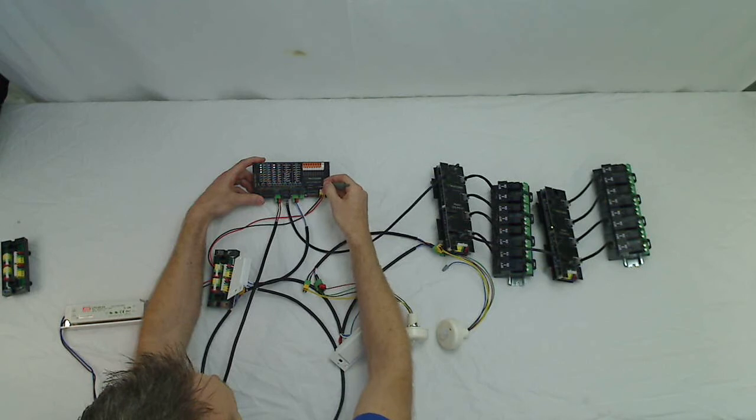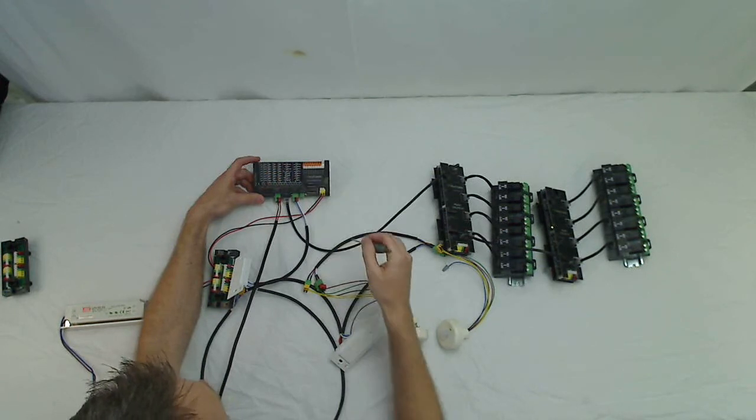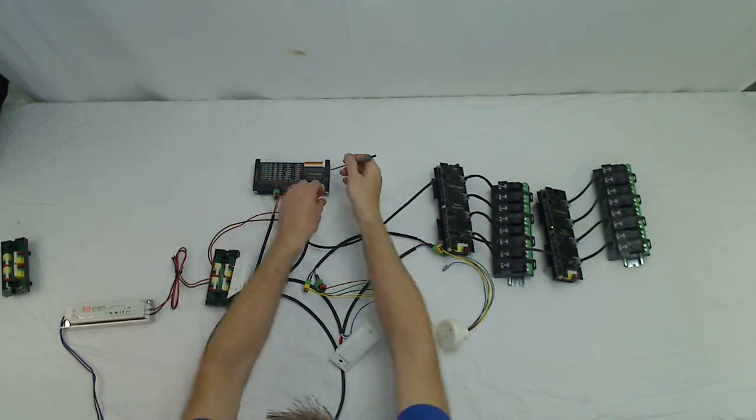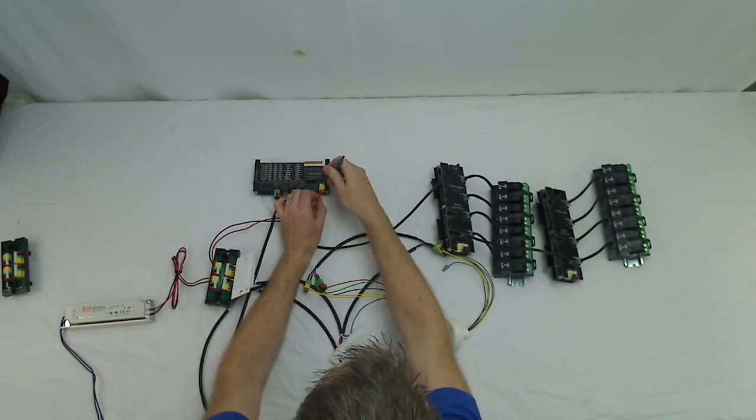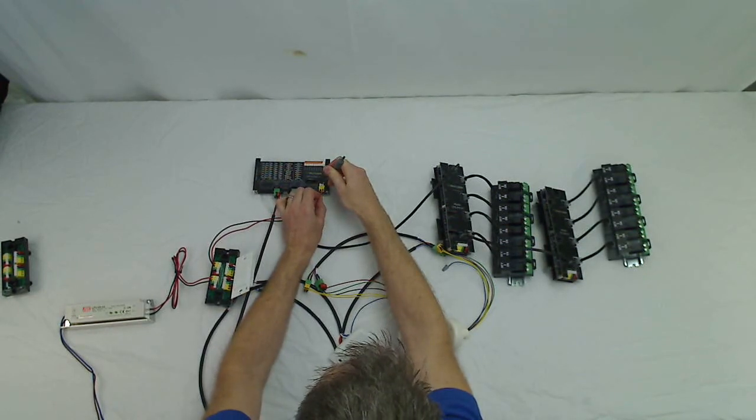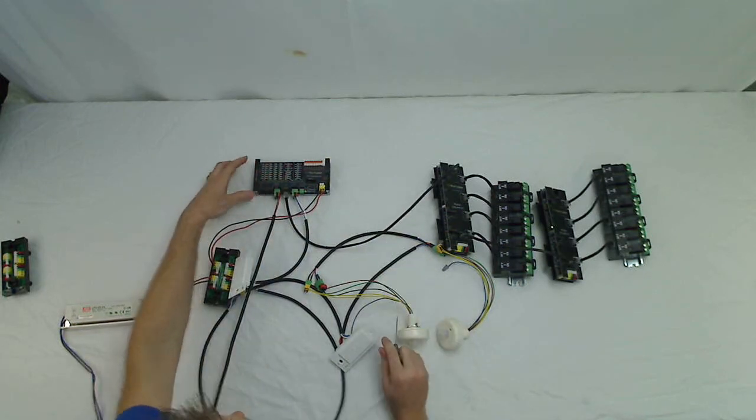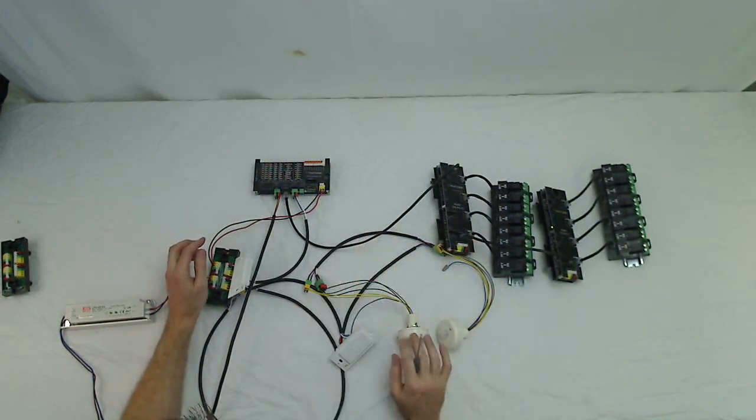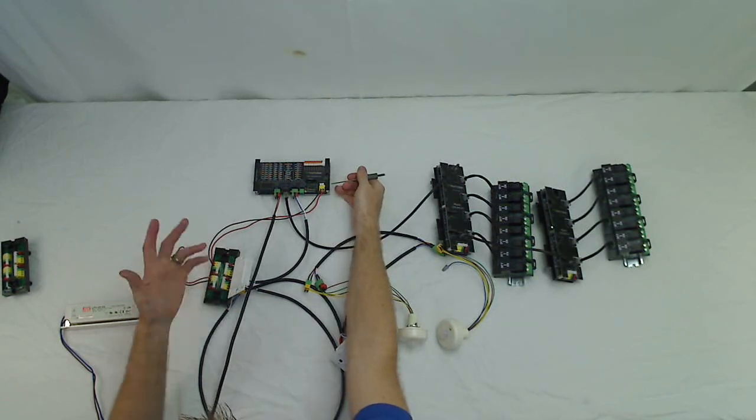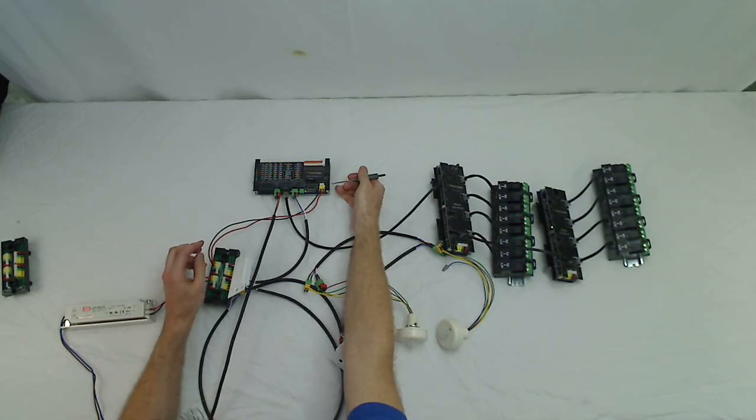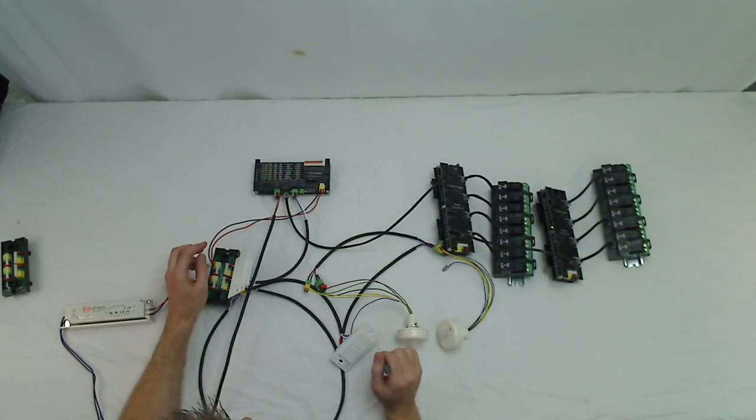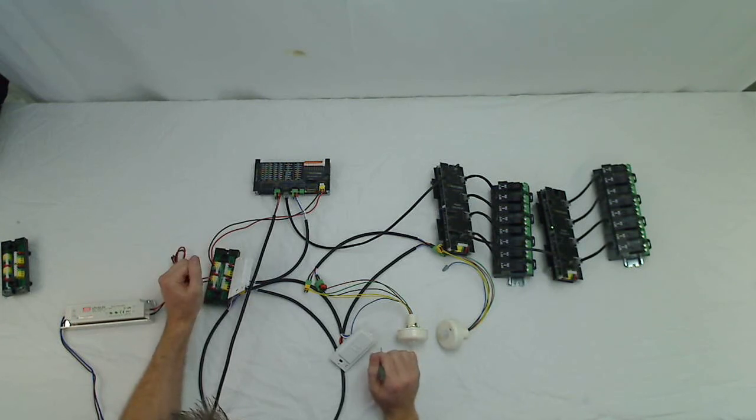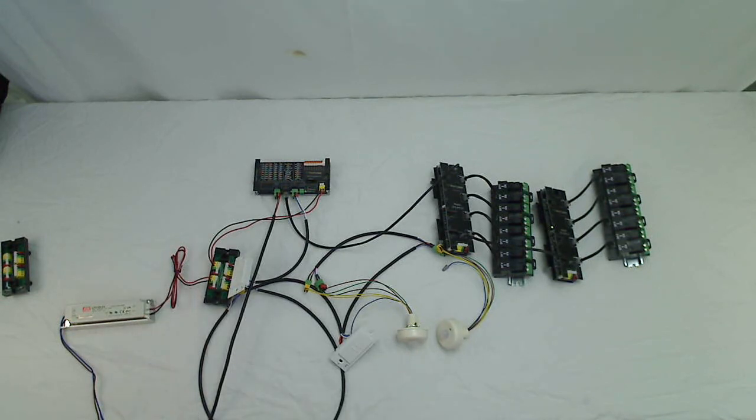So once that's done, to complete it, you just turn off dip switch number seven. And then to complete the process, you need to power cycle the controller. So just pull power and then power back on. And the reason for that is once you discover all the devices with the controller, the controller builds the BACnet object database on a power cycle. So when it powers up all the discovered devices, it will build all of your binary inputs and analog value inputs and etc. for your BACnet communications. Thank you.